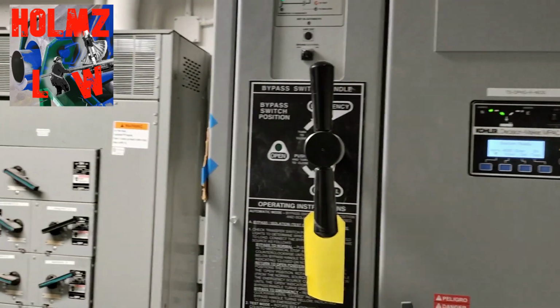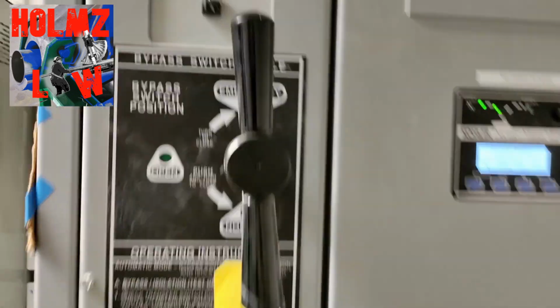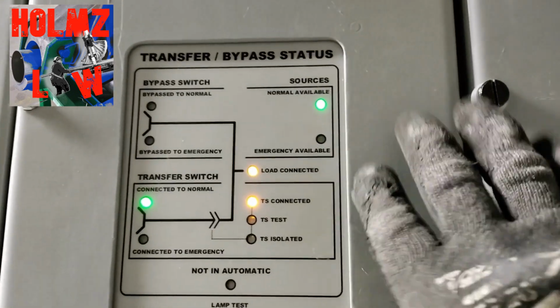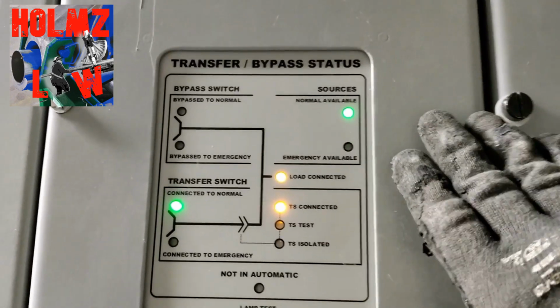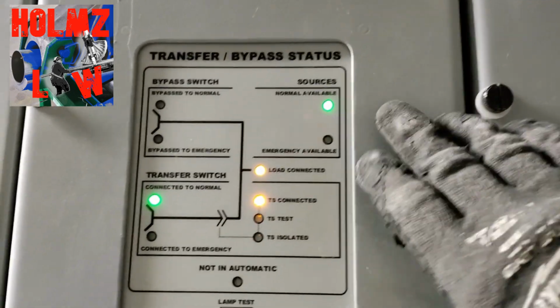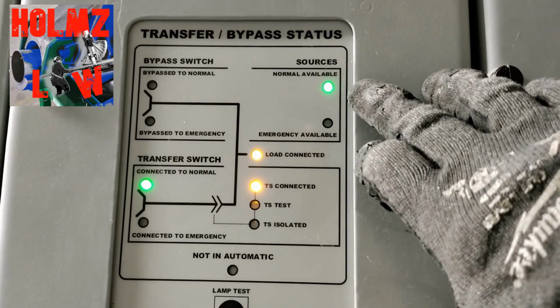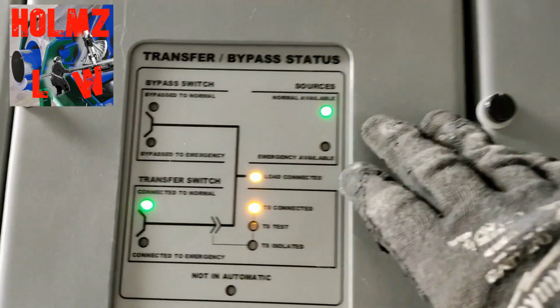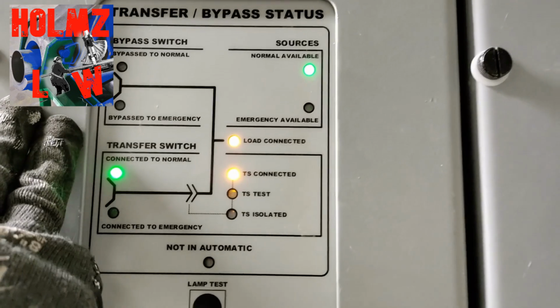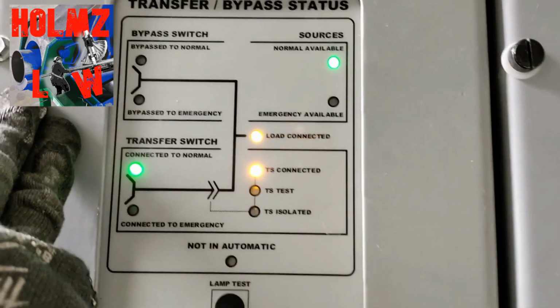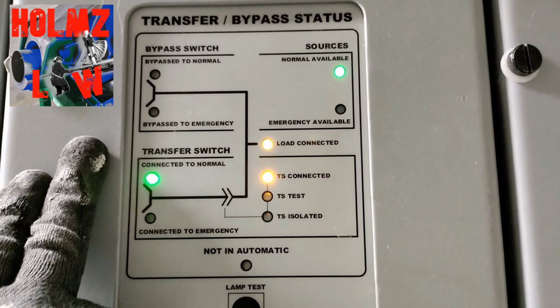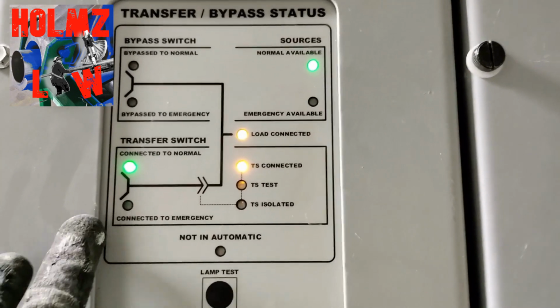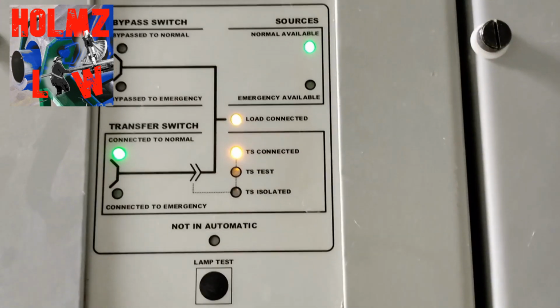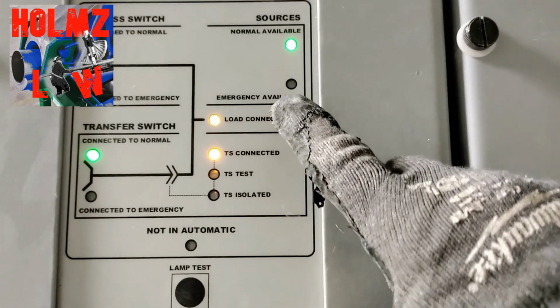Basically, it'll tell you the position of wherever the switch is on, whether it's on the normal source, the emergency source, whether you're on the bypass switch's normal side or the emergency side. It tells you what the status is. You're connected to normal, the transfer switch is connected, and the load is connected.